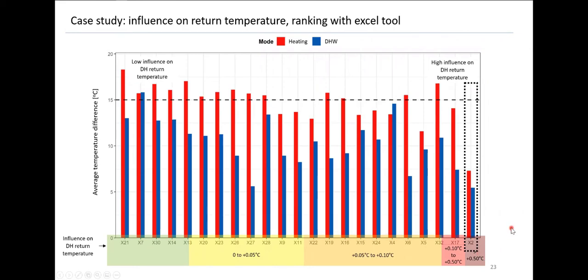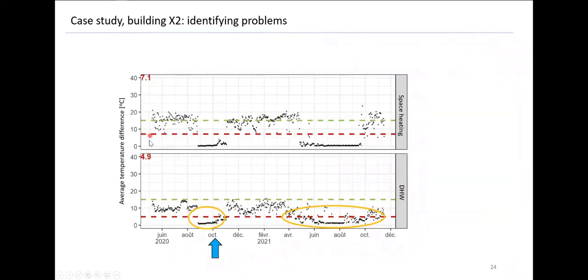Looking at substation x2 in detail, the daily average temperature difference shows the problem is not permanent — some days everything works fine, but suddenly there are days with a very small temperature difference in heating mode. Similarly for domestic hot water mode — the problems occur at certain moments. It's interesting to look at what happens during those problem periods, for example in October, when there is still some space heating demand alongside domestic hot water demand.